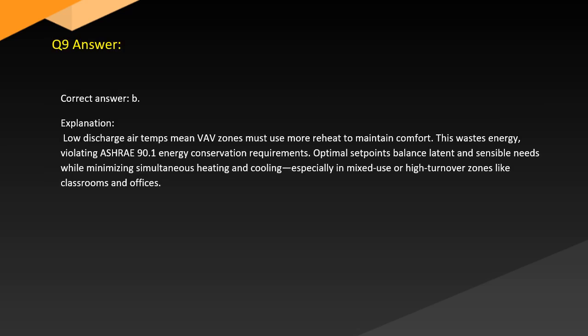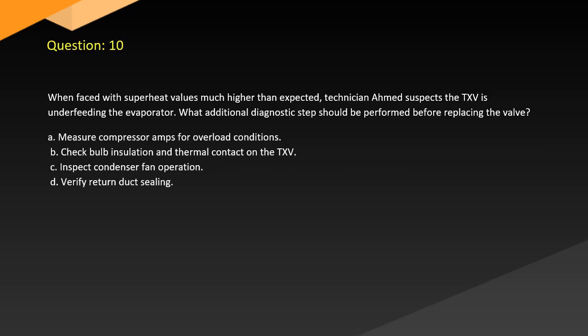Answer. Correct answer: B. Explanation. Low discharge air temps mean VAV zones must use more reheat to maintain comfort. This wastes energy, violating ASHRAE 90.1 energy conservation requirements. Optimal set points balance latent and sensible needs while minimizing simultaneous heating and cooling, especially in mixed-use or high-turnover zones like classrooms and offices.